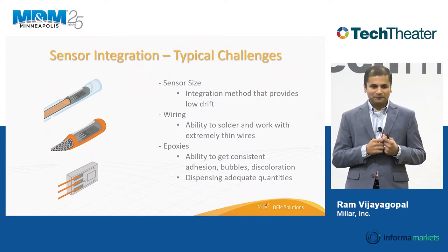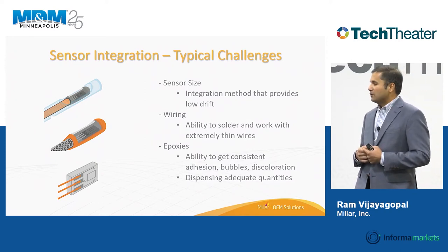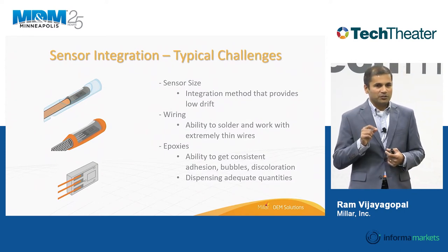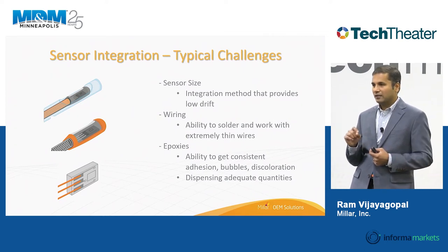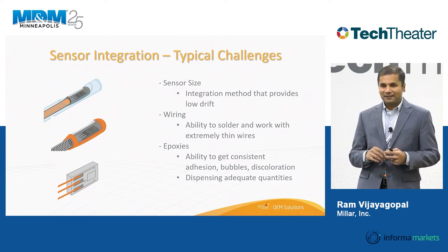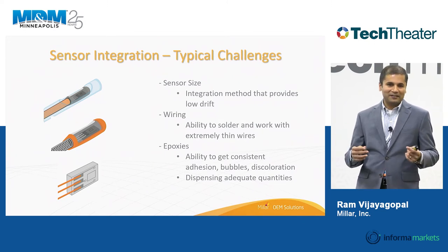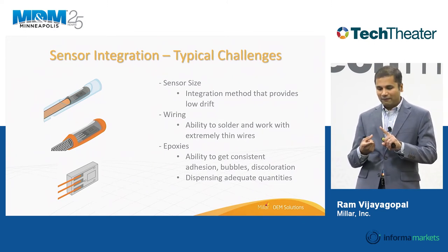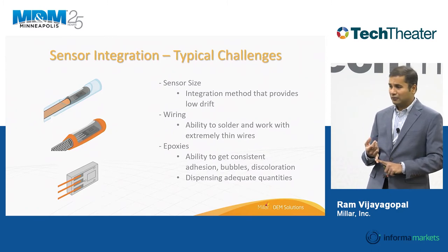Once you've chosen a sensor, you have to integrate it. Sensor integration is very crucial — how you integrate the sensor plays a vital role in its performance characteristics, especially drift. It's one thing to have a sensor, but an entirely different thing to integrate it in such a way that you have good drift performance, good electrical isolation, and it's rugged enough to go through MRI and similar challenges.